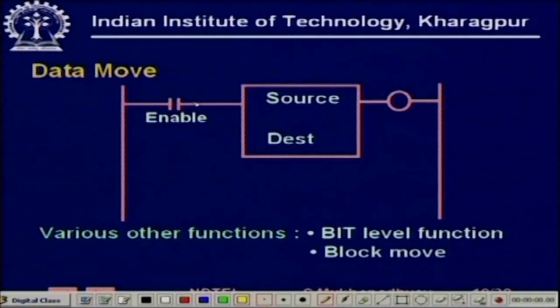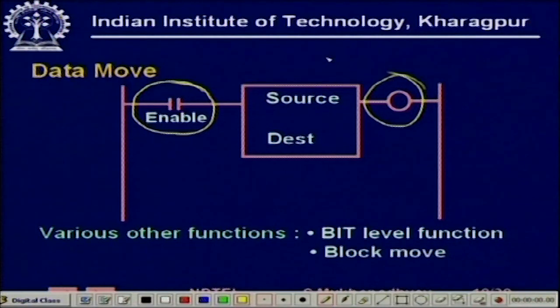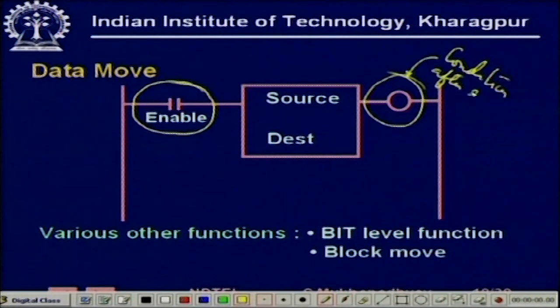Next is data move. Everything is depicted as a rung because in RLL everything is a rung. The data move will take place depending on whether the enabling logic is satisfied. Data will move from source to destination, and if there is some address failure or after the data has moved this output coil can become 1. You can also have bit manipulation functions, various kinds of block moves, and logical instructions.